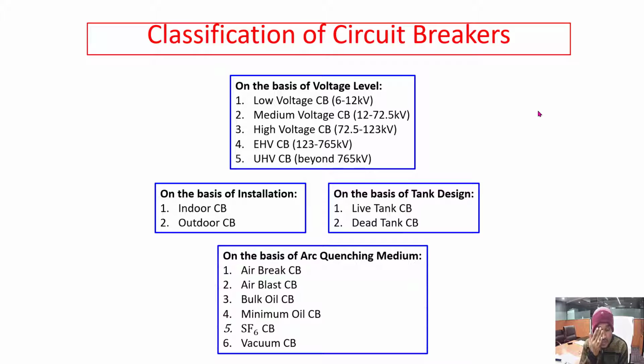On the basis of voltage level, before going into this classification, I should mention that there is no hard and fast definition of what is high voltage, medium voltage, or low voltage. So here for circuit breakers, the classification is given on voltage level. Low voltage is typically 6 to 12 kilovolts, medium voltage typically 12 to 72.5 kilovolts. High voltage circuit breaker is 72.5 to 123 kilovolts. For extra high voltage circuit breaker, 123 kilovolts to 765 kilovolts. And beyond 765 kilovolts, it is ultra high voltage circuit breaker. So this is on the basis of voltage level.